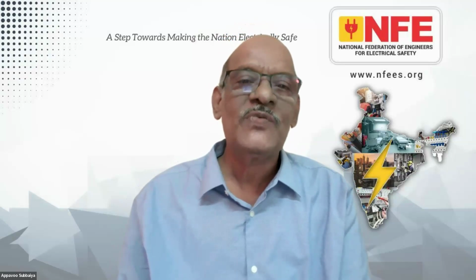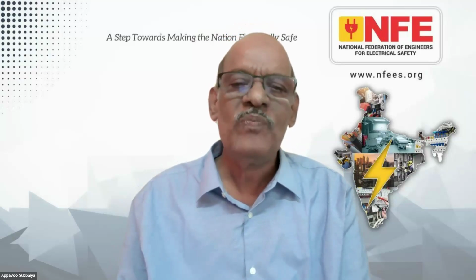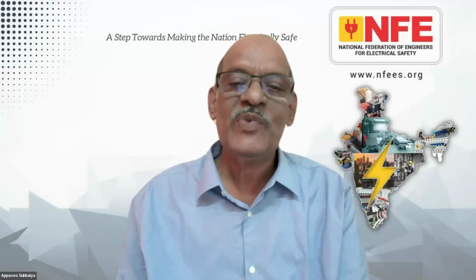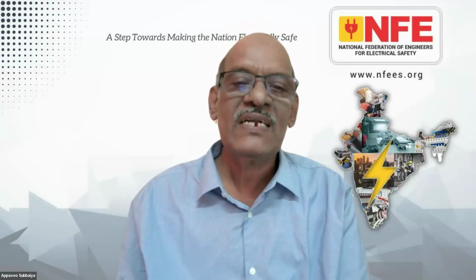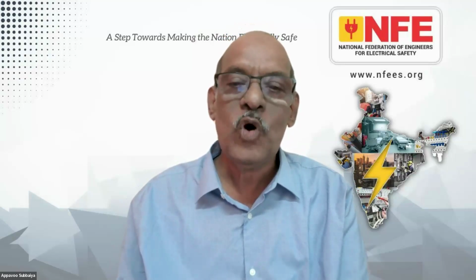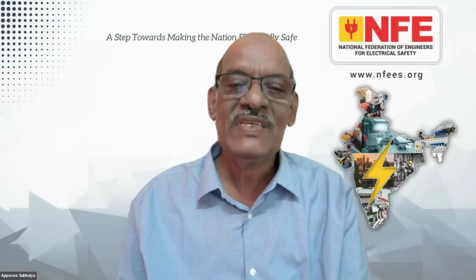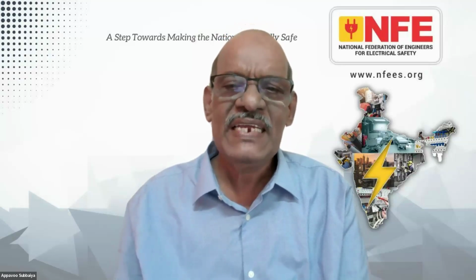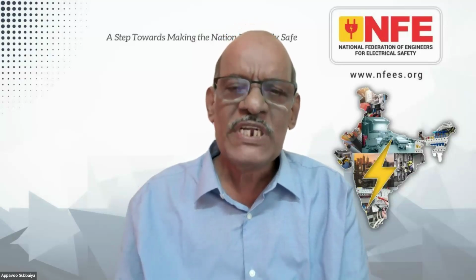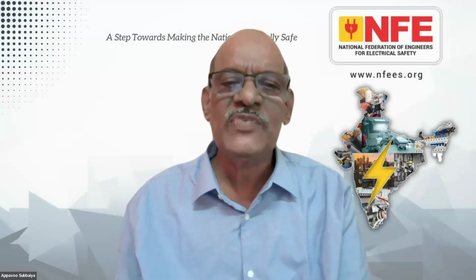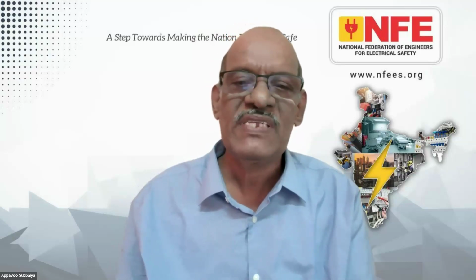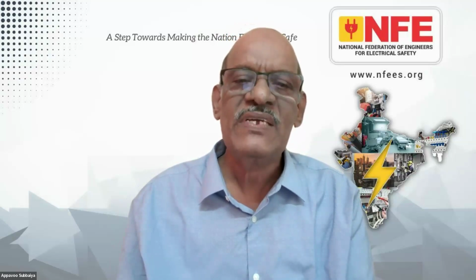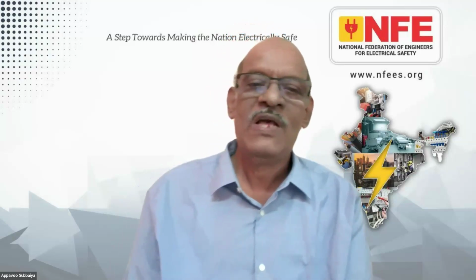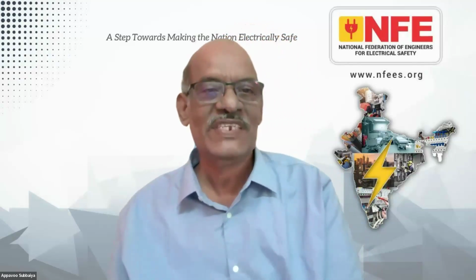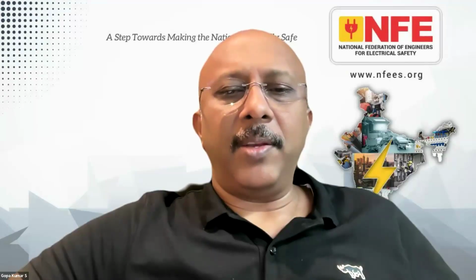The fault loop impedance path is a milliohm path, whereas the earth electrodes constitute several ohms. So the current division to the grid is very small, and your protective device, even your MCB or overcurrent protective device, will take care of shock protection and fire protection. This is a paradigm shift that we have to make, Mr. GK. Thank you, sir.